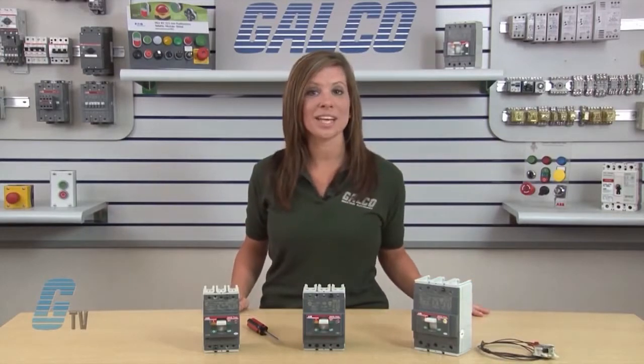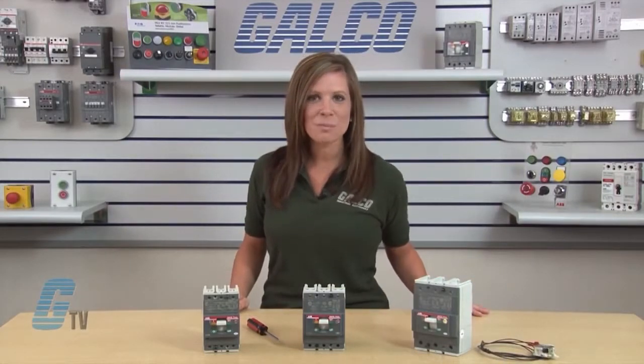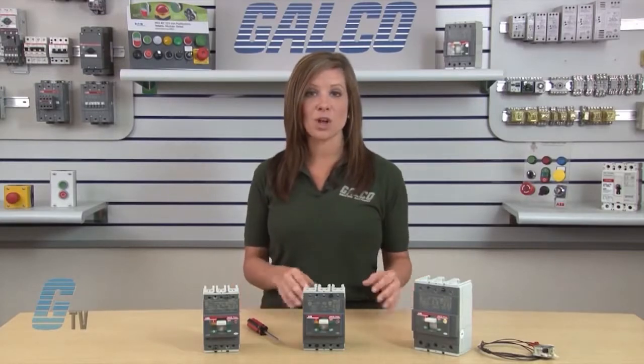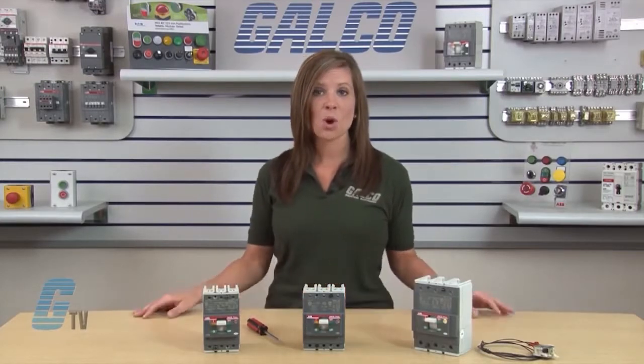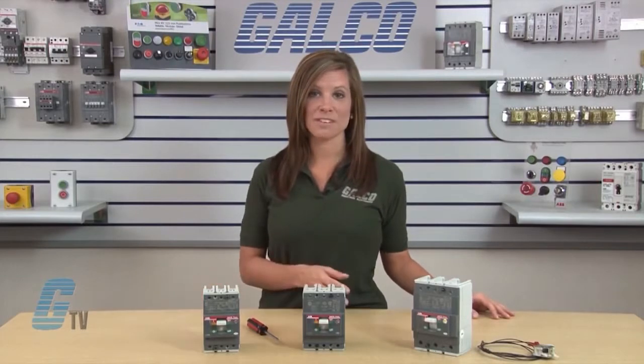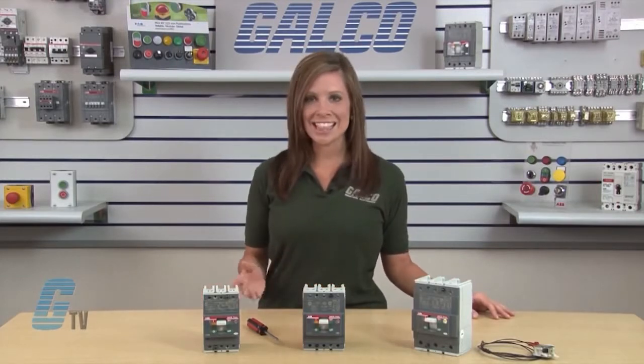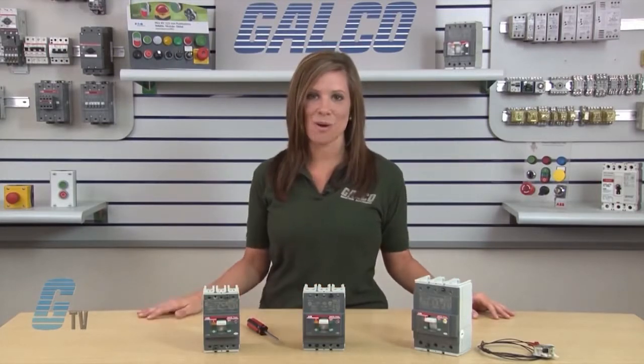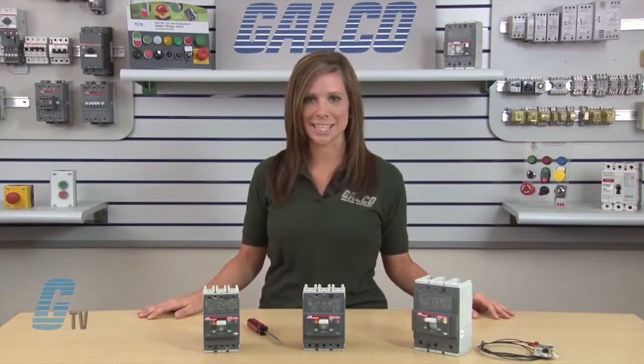Today I will be installing an undervoltage release, or UVR, unit in an ABB TMAX series T1, T2, and T3 enclosed circuit breaker. Circuit breaker accessories should only be installed with the breaker out of circuit or when all power has been removed from the device, control panel, and anything nearby that may be a hazard to the qualified electrician doing the installation.